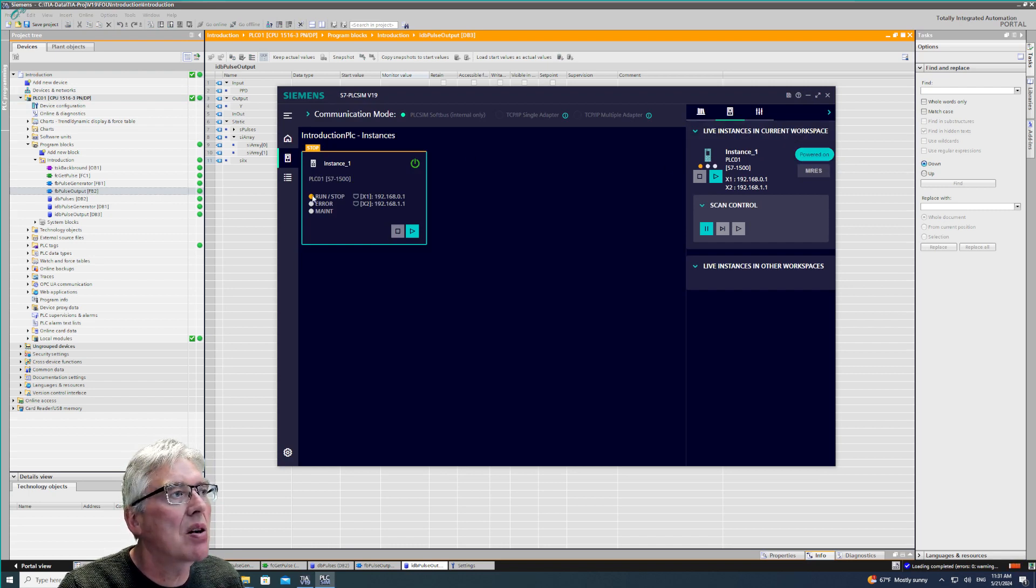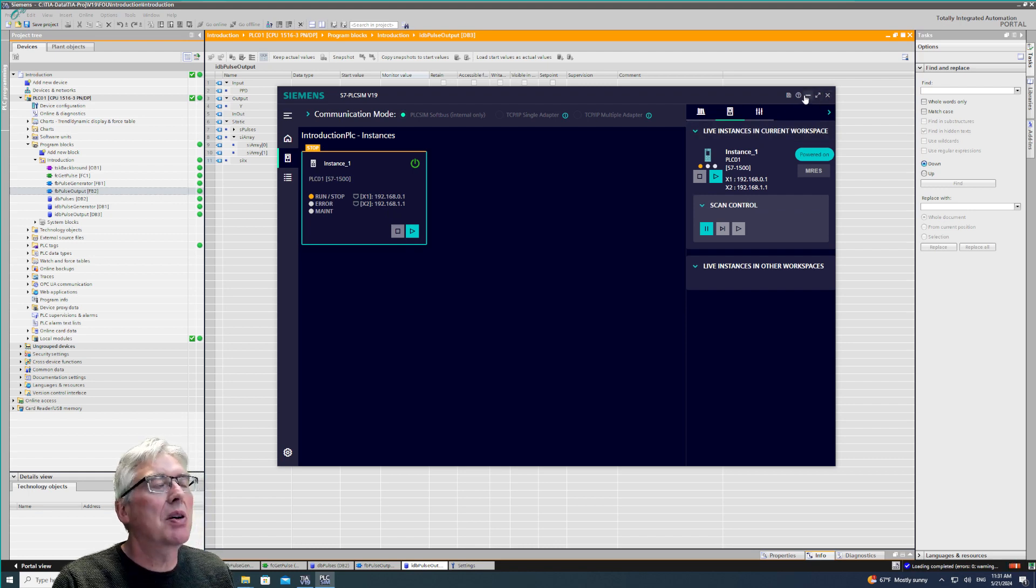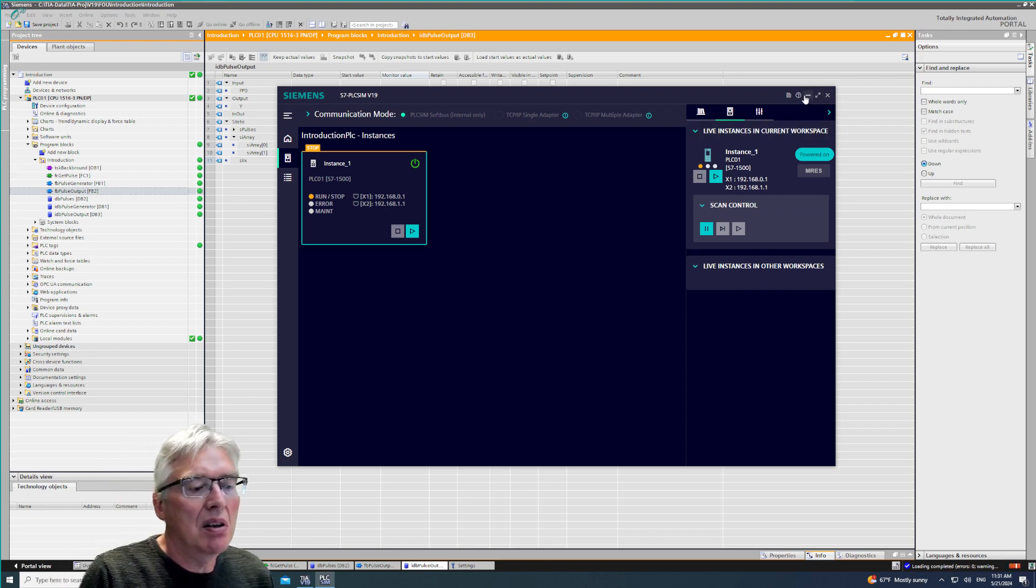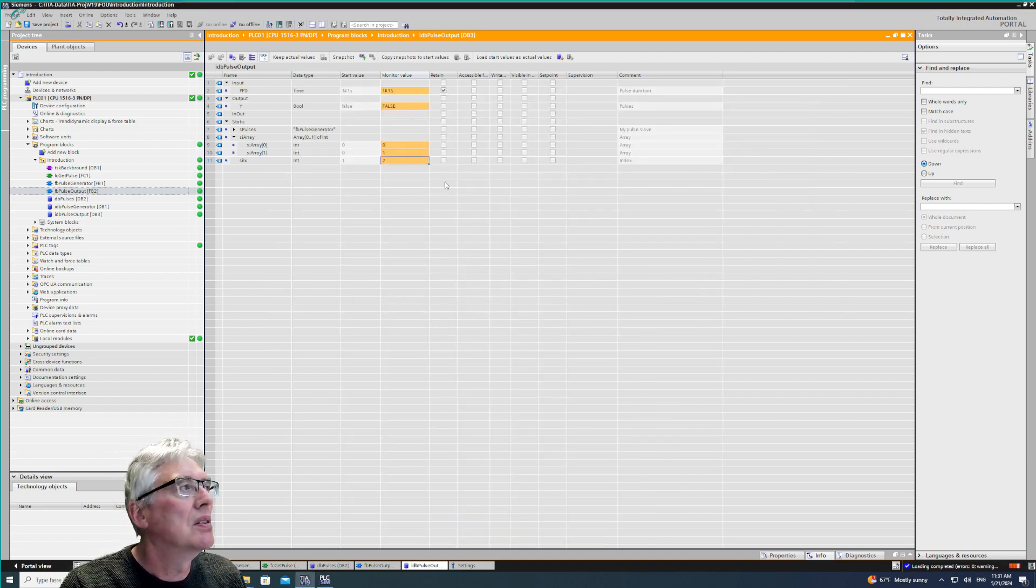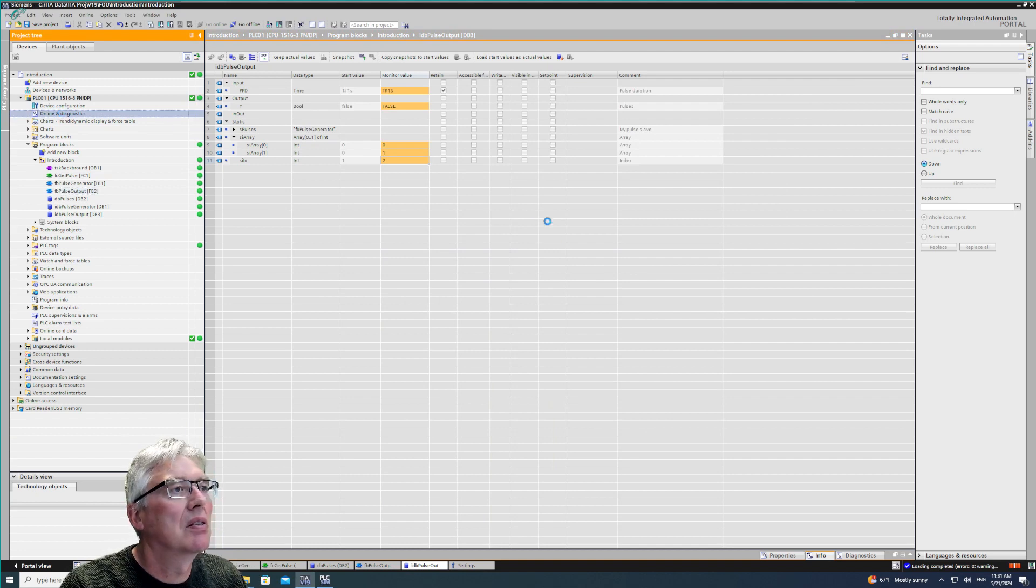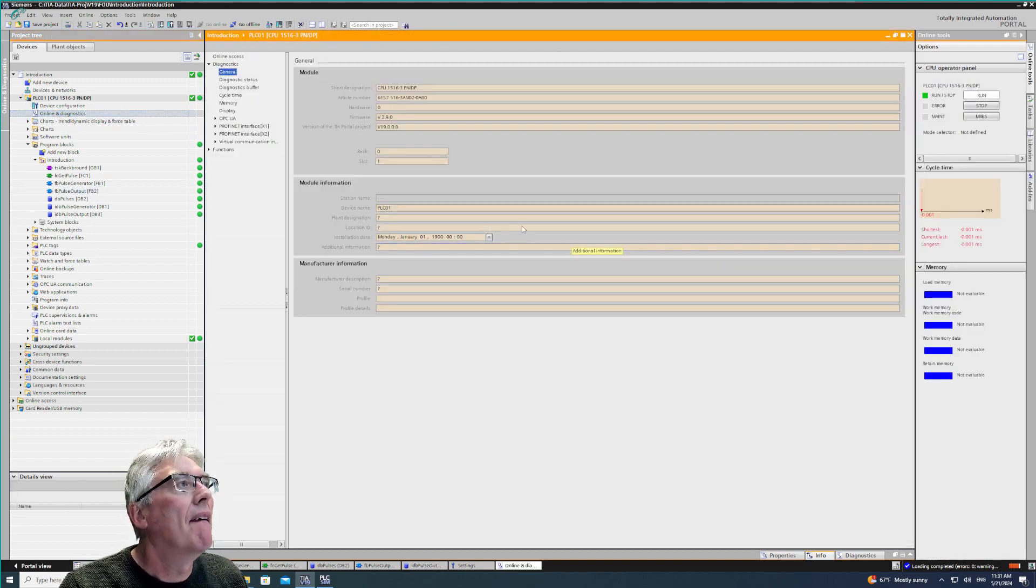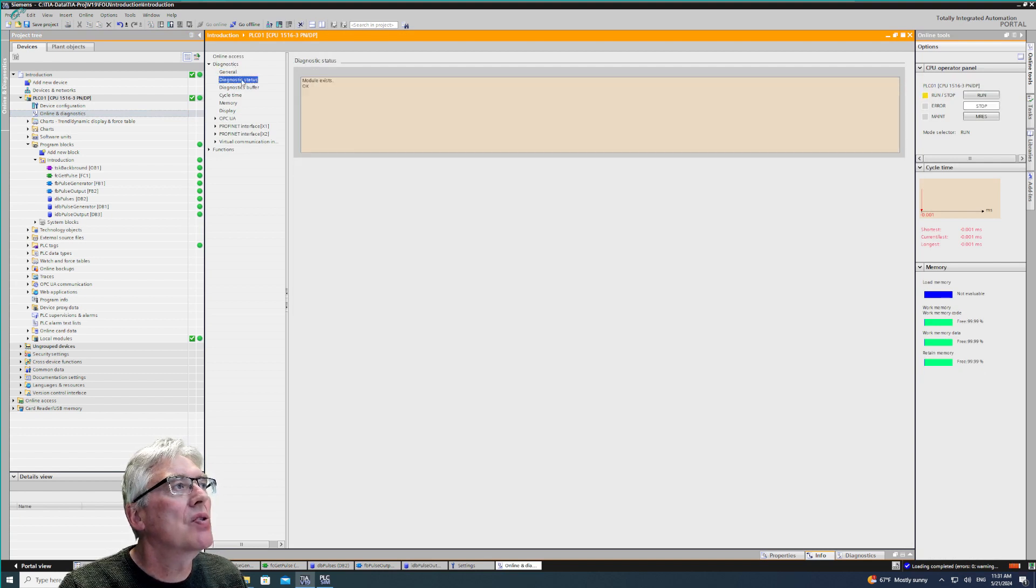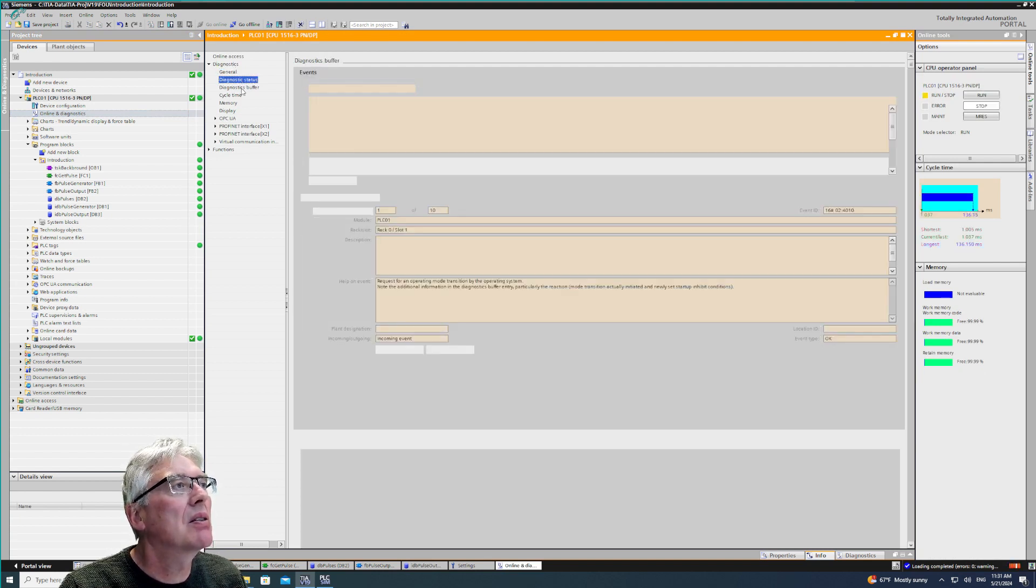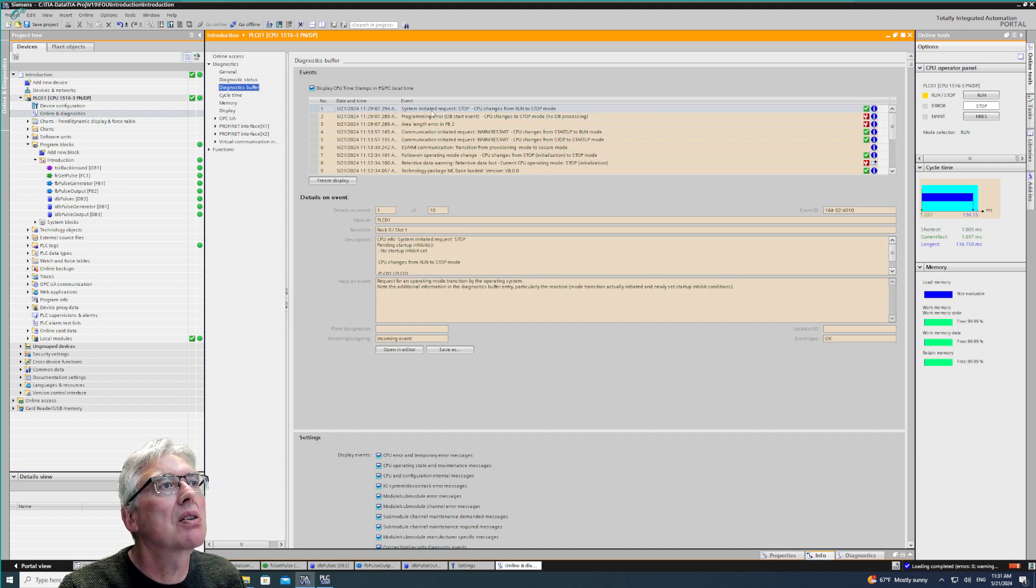Nothing happened. I got a message here. Oh yeah, the PLC simulator is powered on, it's yellow, it has stopped. So this program error, I tried to access the memory that doesn't exist. The default is the CPU goes to stop mode.